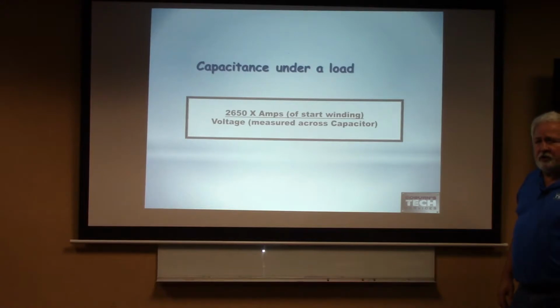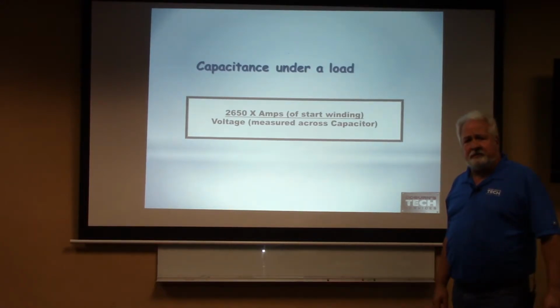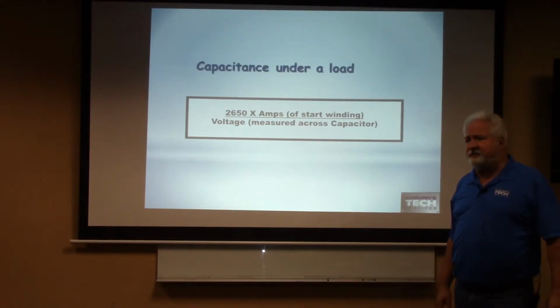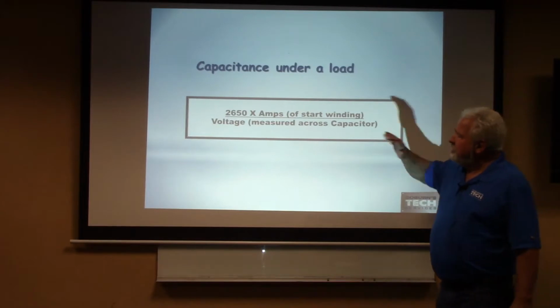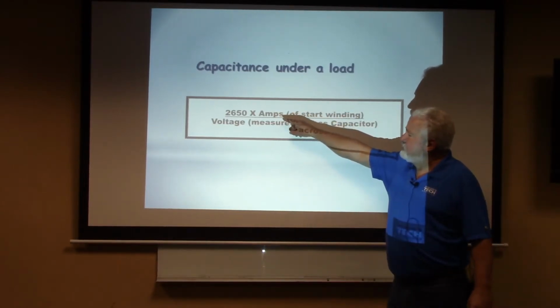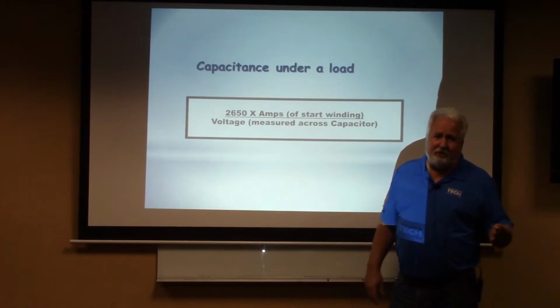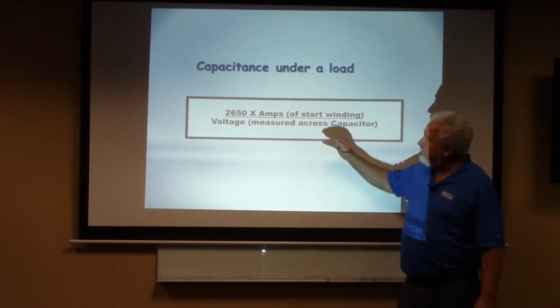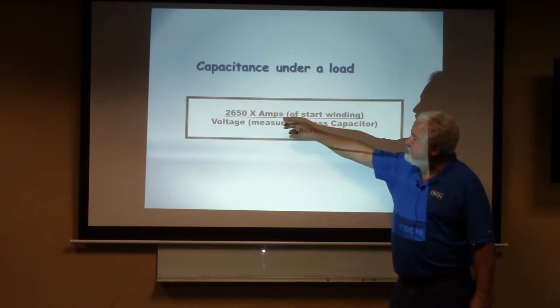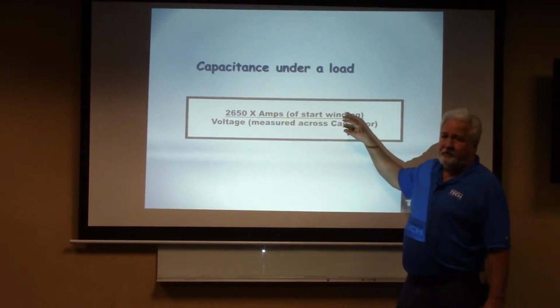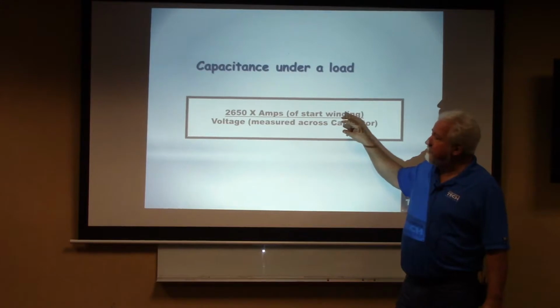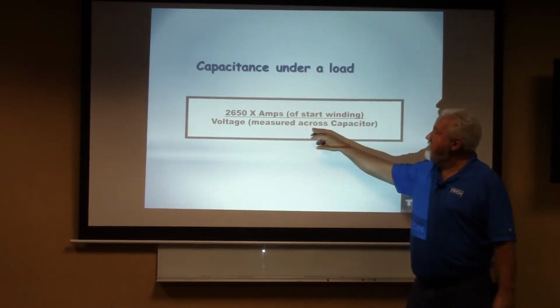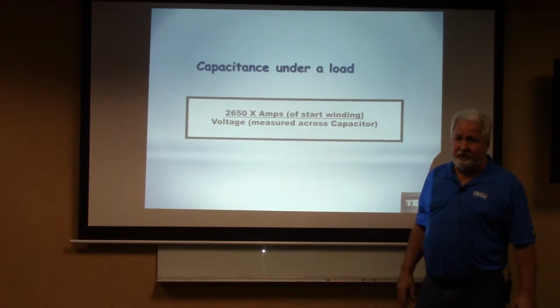Well, you can check your capacitance on that unit while it's running. So instead of having to turn off the entire system, ohm out that, put the capacitor checker on that capacitor, you can check it while it's running. The formula says 2650 times amps divided by volts. What they don't do is tell you what amps of and what volts of. So here I added this in. 2650 times the amps of the start winding. So you get the amperage of the start winding, and then you divide it by the voltage measured across the capacitor. Everybody good with that?